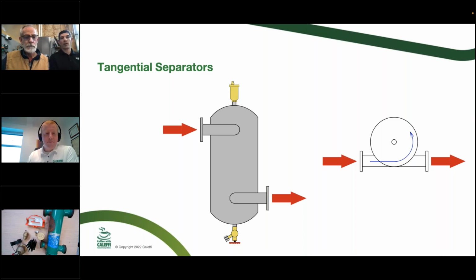So in the hydro separator, when the water goes into it, it slows down to about 1/9 of the velocity in that big chamber, and that's how we really effectively separate the air too, is that we just give it time to slow down so it can come to the top a little bit easier.